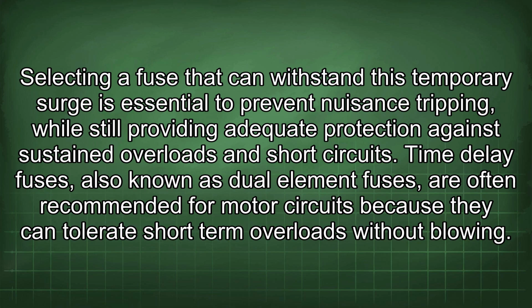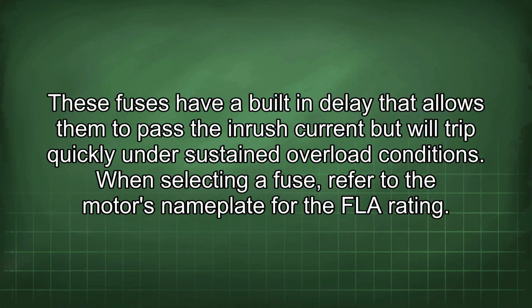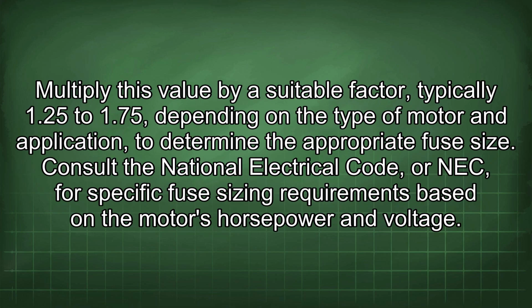Time delay fuses, also known as dual element fuses, are often recommended for motor circuits because they can tolerate short-term overloads without blowing. These fuses have a built-in delay that allows them to pass the inrush current but will trip quickly under sustained overload conditions. When selecting a fuse, refer to the motor's nameplate for the FLA rating. Multiply this value by a suitable factor, typically 1.25 to 1.75, depending on the type of motor and application, to determine the appropriate fuse size.